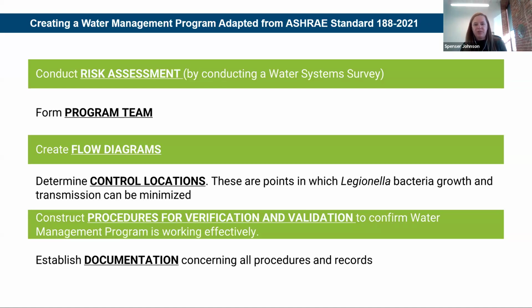The first thing you want to do is conduct a risk assessment at your facility, surveying the entire facility: how many points of entry you have, how your hot water is heated and stored, how many recirculation lines you have, what types of fixtures you have. Like Brian mentioned earlier, do you have automatic faucets that may need to be purged more often, do you have laminar flow aerators, making sure water is moving throughout the building.